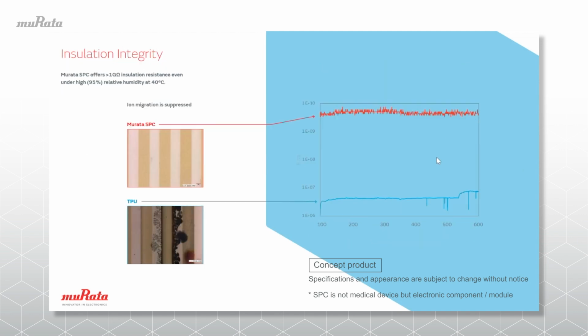Wearable patches and devices are often used for a long period of time directly on the skin, which can be a challenging environment in terms of the humidity, fluid, and high temperature that the devices can be exposed to. Traditional stretchable printed circuits are often based on a substrate material called TPU. One of the downsides of TPU is that it has a low insulation resistance under high humidity circumstances, meaning that especially with high humidity and high temperature, ion migration can occur, creating short circuits between tracks, as you can see in the pictures on the left.